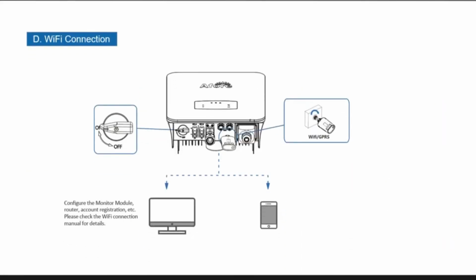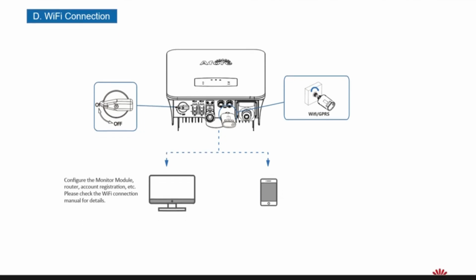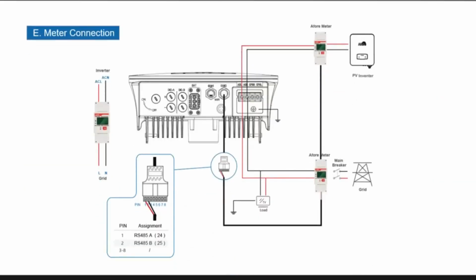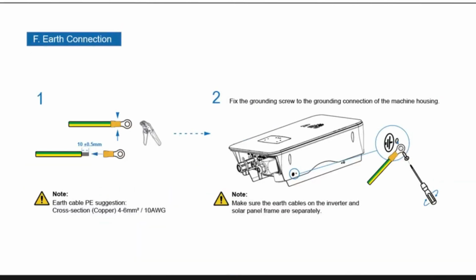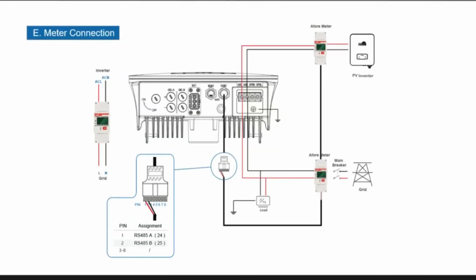AC connections for your live in, neutral in, essential circuit supply, neutral and live in. And obviously on the bottom, the isolator on the bottom of the AC coupled system. And then you can see on here, if you use a meter, the meter connection goes in 1 and 2 in the green plug. And if you use CT, the connection goes into 7 and 8 on this plug.